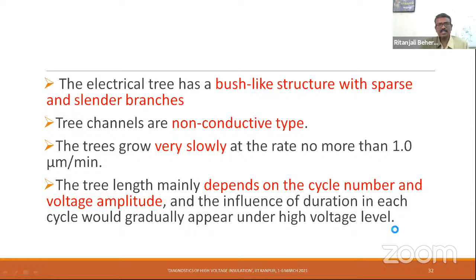The electrical tree under harmonic high frequency voltages: the transmission of AC power through underground cable is more prominent, but because of the presence of converters at either end in an HVDC system, the converter transformer and cable go through not just DC stress alone but also a superimposed harmonic presence. This study helps us understand the effect of AC voltage with harmonics present on the breakdown mechanism of the insulation system.